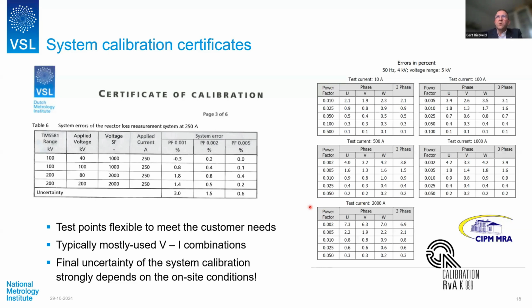So this is how a calibration looks: an applied voltage for a certain current, and then errors as a function of power factor. For a reactor system, it is low current, but for a power transformer system, the current goes up to 2,000 amps. You can see here a certain voltage, a certain current, and then as a function of power factor, the errors of the different ranges, and then the 3-phase total error of the system. What we typically do is that these test points are agreed together with the customer, because we want to be sure that we take those test points that they mainly use in the verification of their products.